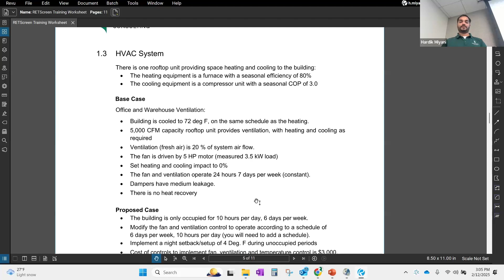Now in the proposed case, as an energy auditor, I am recommending, if this is an office space, it won't be occupied 24/7. Why are you operating during unoccupied hours? So what I will recommend to the client is, why don't you implement a scheduling measure, right? Or optimum start stop, right? Optimum start stop, is everyone aware of optimum start stop? What it is? No? Okay.